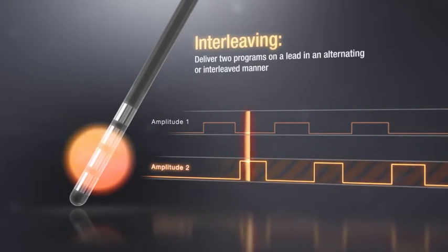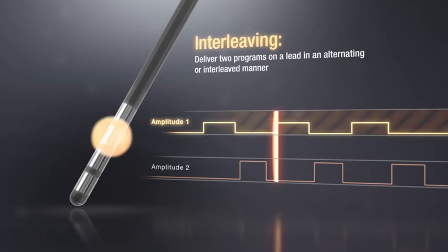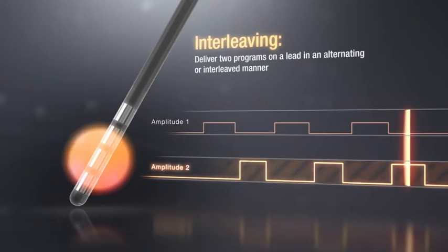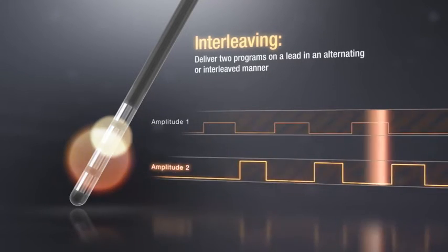The interleaving function found in Medtronic's DBS platforms, all conventional single-source systems, create two settings or programs on a lead where the contacts can be configured with different amplitudes and pulse widths. The pulses from these settings are delivered by alternating between the two settings in an interleaved manner.